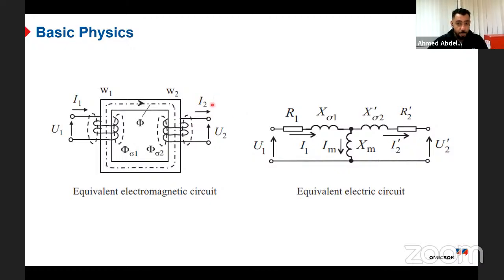So we have here U2. The flux is divided into three parts. The first part is the main flux, phi, which is responsible for inducing the EMF on the low voltage side. But there is also phi sigma 1 and phi sigma 2, which we can consider as losses. As we know, in every system we have losses. So the losses in the magnetic field here are phi sigma 1 and phi sigma 2. This is what we call the equivalent electromagnetic circuit.